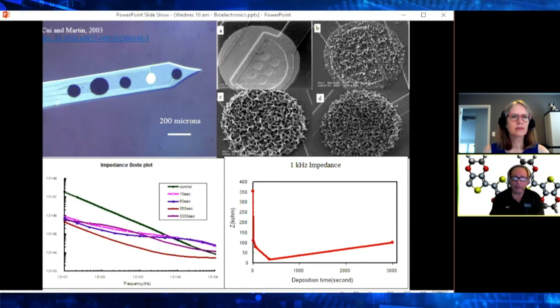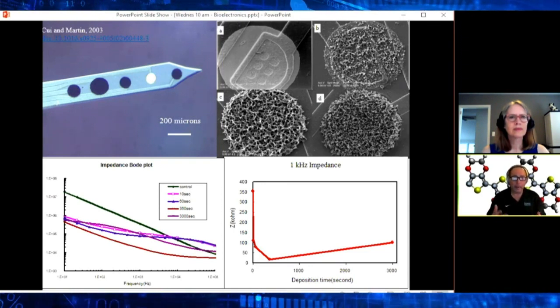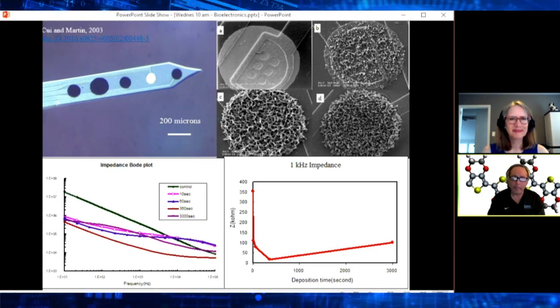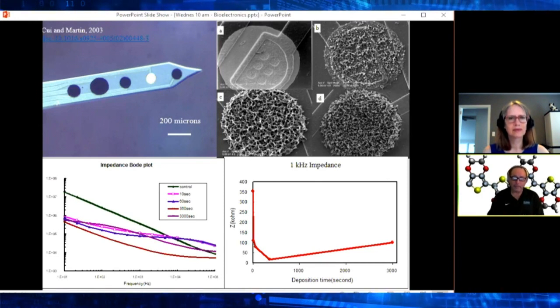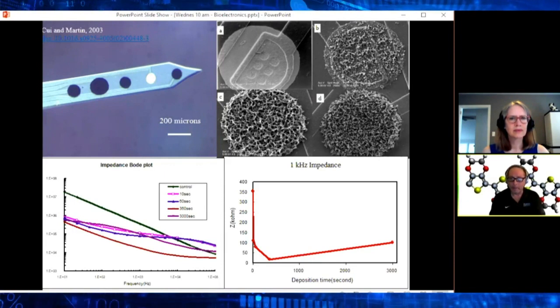So you're looking at 5 little electrodes, and we've coated 4 of those electrodes with more and more conjugated polymer. So the polymer is very dark black, and as you put more and more of the polymer onto the electrode, it gets sort of fuzzier and hairier. So in the upper right-hand corner, you can see scanning electron micrographs of these coatings as they get thicker and thicker. And you can see just from looking at it that what's happening is we're creating a film that's got a lot of effective surface area. And so the performance of these devices is really critically tied to this increase in the overall amount of surface area that can interface from the metallic electrode at the bottom to the ionically conducting tissue that we're trying to communicate with.